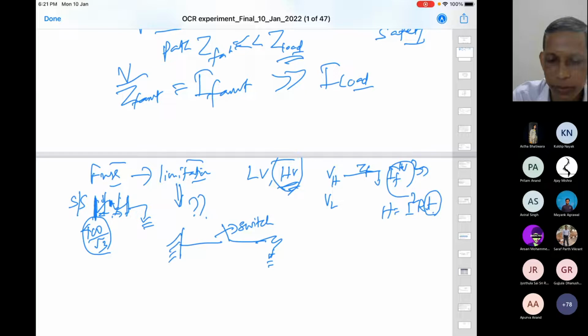If this fault continues, large current will flow through the lines, adjacent buses and lines will also be stressed, and voltage may dip in and around those places. So we will not allow this faulted path to remain. The customers around that feeder will be affected, and in addition, everything in and around that place will be affected. So it is better to isolate the corresponding faulted path as early as possible.